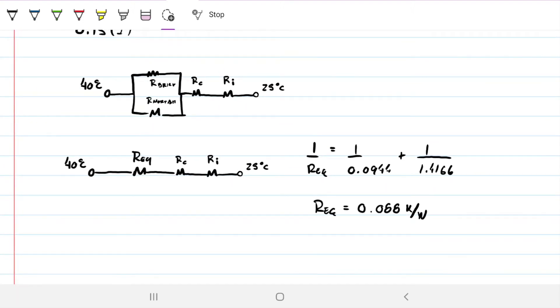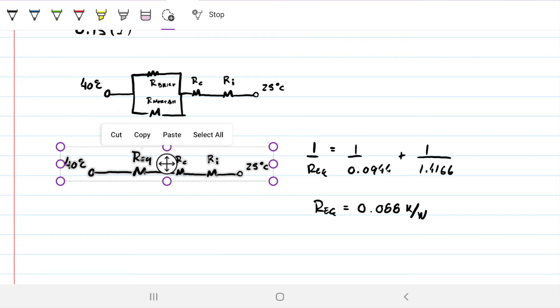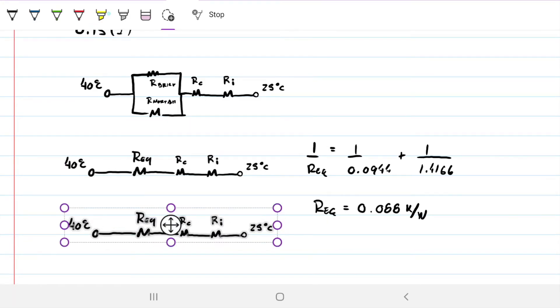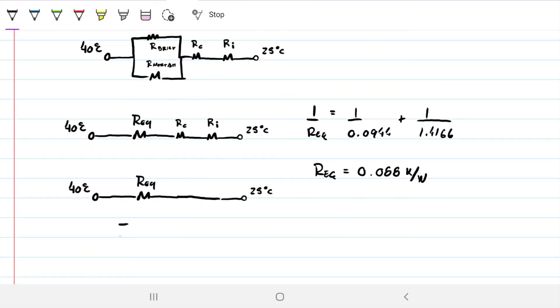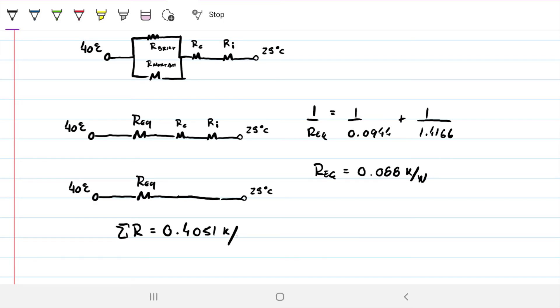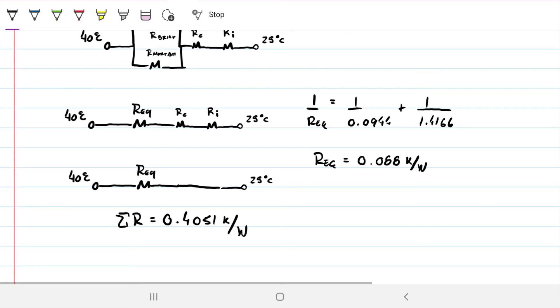Next, we sum all series resistances into a single total equivalent resistance. We add the parallel brick-mortar result (0.088 K/W), the insulating board (0.0666 K/W), and the concrete (0.25 K/W) to get a total equivalent resistance of 0.4051 K/W for the whole wall assembly.